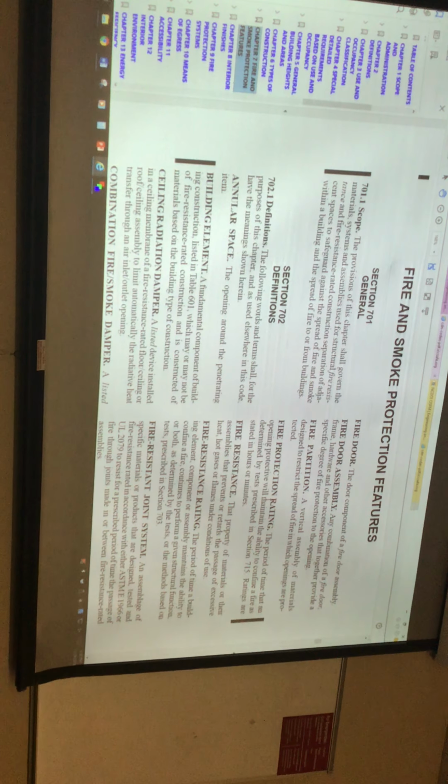If you're in this high-rise building and the fire alarm goes off or the smoke detectors go off, that elevator is going to respond to the floor that had the detectors go off, 2 floors below and 2 floors above, and those are the only floors it's going to go to. If you're on one of the other floors, that elevator's not going to stop for you. It's going to go right to those floors, get those people, and take them right down to the bottom because they're the most at risk. If you're on one of the other floors, you still have to go to the stairs.